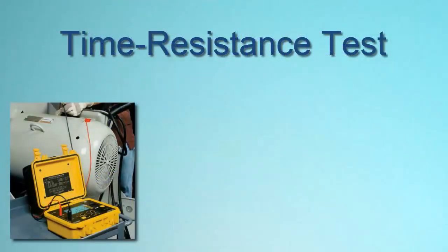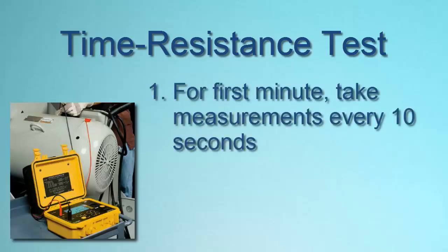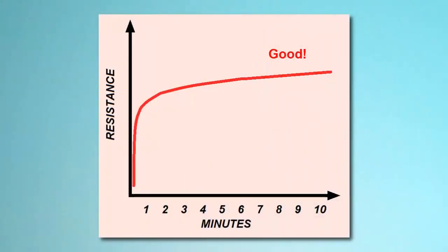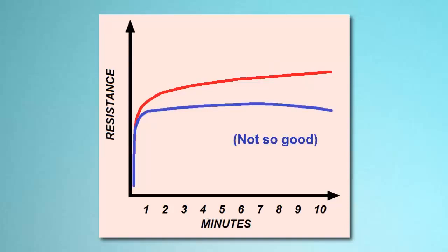Another insulation resistance measurement method is the time resistance test, also referred to as the dielectric absorption test. It involves conducting a 10-minute test. For the first minute, during which absorption current will have the highest effect on resistance, measurements are taken every 10 seconds. After the first minute, measurements are taken once per minute. When you plot the results, you should see a curve that rises relatively rapidly at first, and then continues to gradually rise throughout the testing period. If instead the curve is relatively flat or begins to turn down as the test progresses, moisture, dirt, or other factors may be compromising your insulation.